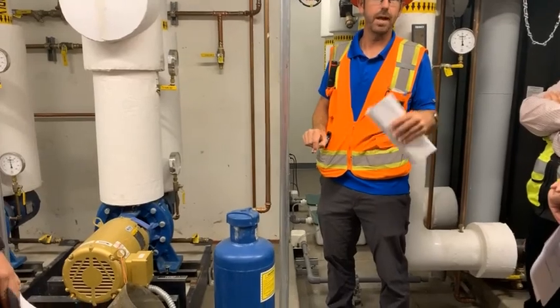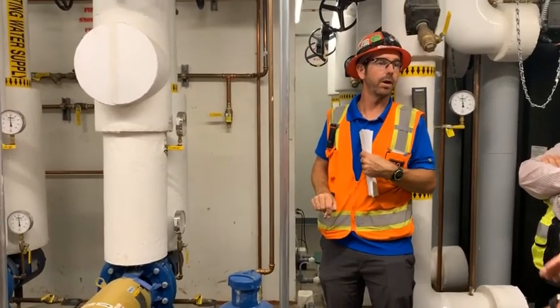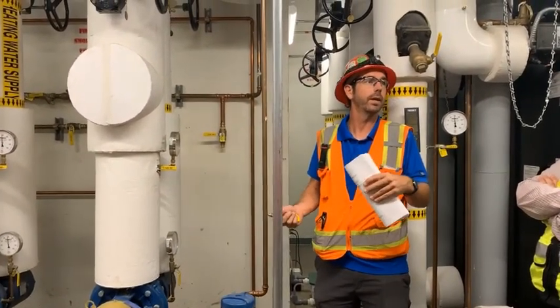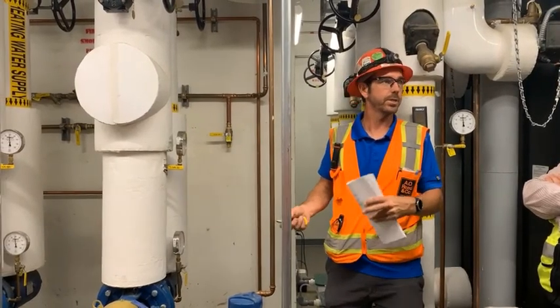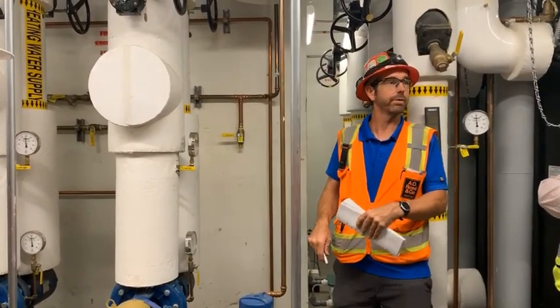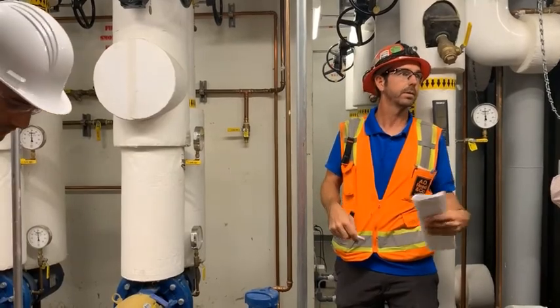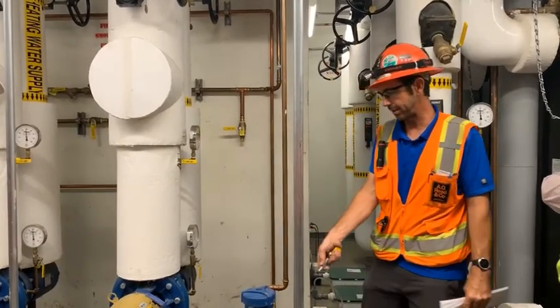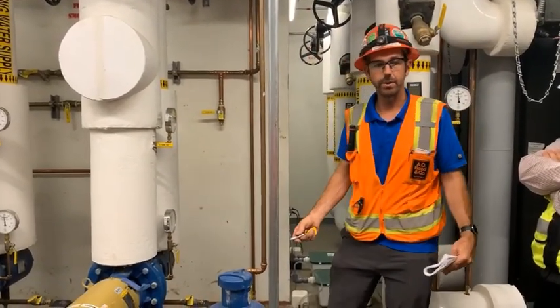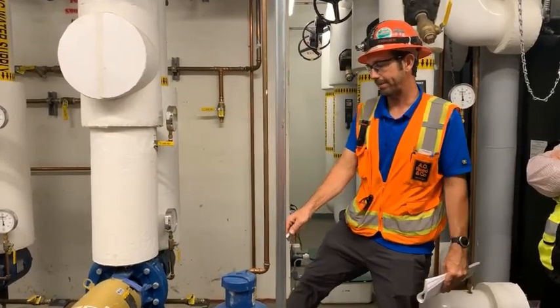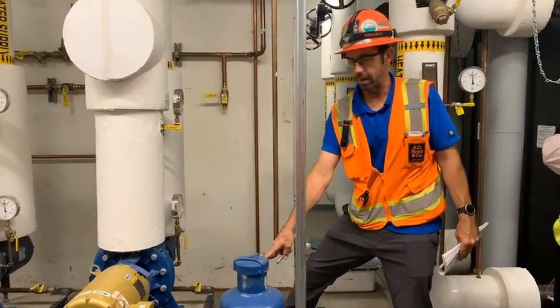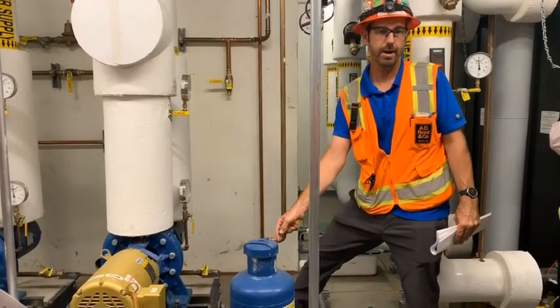Just make sure if it's not the same company that we did our startup with, whoever's coming in does a water analysis and makes sure that their chemicals are compatible, or they flush the system and then add theirs. That's another way of doing it too. But this is your pot feeder for that. They've always told me never to close it all the way off because it's a steel drum. You always want a little bit of flow. That's why this valve is kind of cracked, okay?